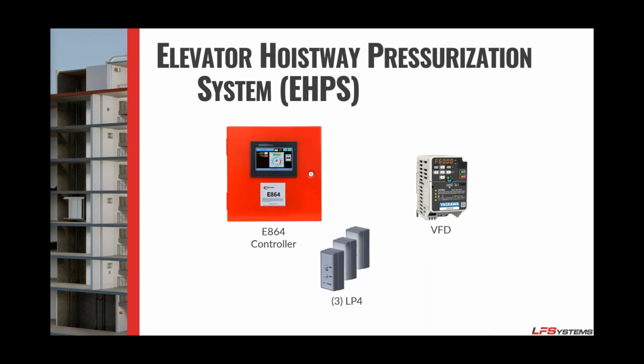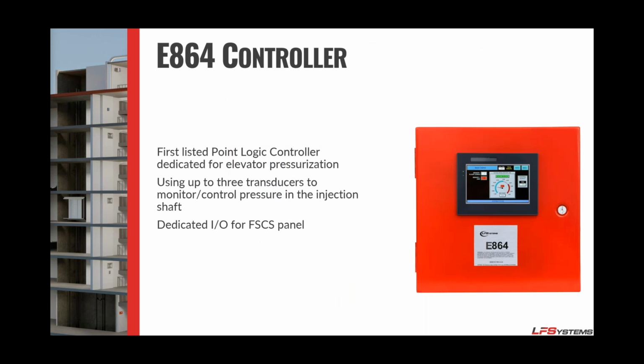The system includes the controller and 3 transducers. We prefer to provide the VFD, not because it's anything special, but because it is already programmed to match our controls. If you have a building that requires Allen Bradley, Danfoss, or ABB, a specialty brand that they want to make sure everything matches, that's totally fine. Just know that the drive will have to be programmed by that provider to match what we need. Again, the E864 up close: 7-inch touchscreen, with a dedicated input and output for the FSCS as required by code.